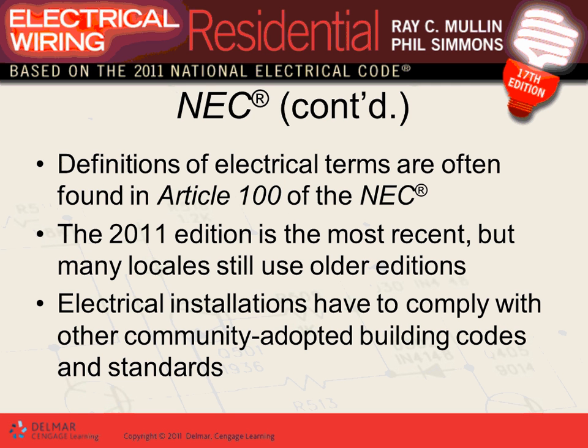The NEC code book, if it's confusing for you, here's one little thing. When I teach you the NEC code book, the first major thing you need to know is the definitions. Because later on you're going to be sizing something called an ungrounded conductor. What's an ungrounded conductor? It's the hot conductor, in plain English. You need to understand equipment grounding conductor versus grounded conductor. Grounded conductor is the neutral. Equipment grounding conductor is what we call a ground. So you get into the whole terminology, and I'll go over as many of them as I can with you guys as we move through.